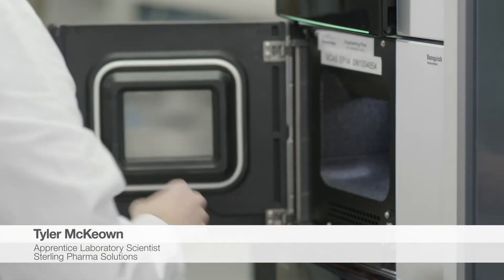A lot of different things stand out — personally, the manual operation buttons allow, if you are logged out of your Chromeleon account, the Thermo Scientific Vanquish Core has buttons which can turn it off manually without using the software.